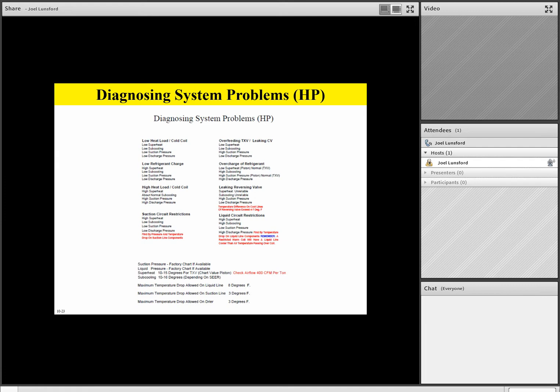And in the heating mode of operation, we want to see about 15 to 25 in the heating mode of operation. Now, as we continue looking at our parameters right now, team, remember the maximum temperature drop we're going to allow on the liquid line will be 8 degrees as we take a look at our diagnostic screens today. The maximum temperature drop we're going to allow on any suction line in the cooling mode of operation or in the heating mode of operation, that cold suction line leaving the cold coil, should not exceed 3 degrees.